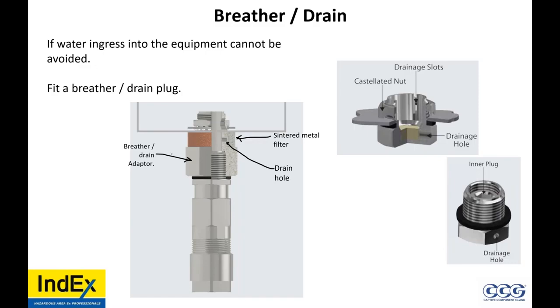Now, breather drains. If water can ingress into an equipment and that cannot be avoided, put in a breather drain. Now, the thing is, do all end users call for it in their specifications? Perhaps not. Do all EPCs use them? Perhaps not. Would you always use them on an EXP panel, a control panel, a distribution board outside? Most end users do call for it.